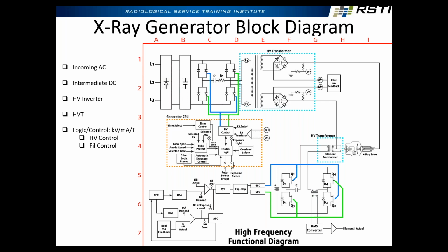Rectifying. I'm taking that 480 3-phase and making a DC voltage, 600, 800, 1000 volts or whatever. Why am I doing that? Faster, more efficient, easier to control. I'm then taking DC and running it into the inverter, whose job is to do what? Chop up that DC and pass it to the high voltage transformer, because you can't pass DC through a transformer. So we've got to chop it up, make it look like AC, and then we can pass it to a transformer.